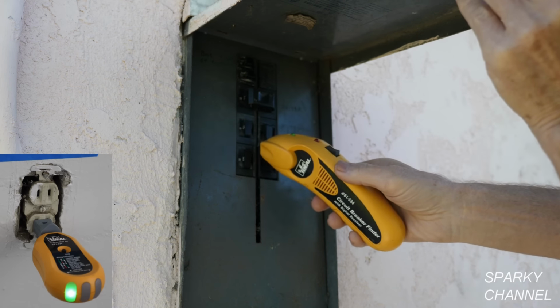Now I need to find out which one of the receptacles on this circuit of 7 receptacles is most upstream, because that is the position where the ground fault circuit interrupter is going to go. It's going to go on the most upstream receptacle. Now, your first thing you do is look and see which receptacle is closest to the main panel. And 95% of the time, I'm telling you, just as an electrician, that's the way we wire things. This would be my guess.